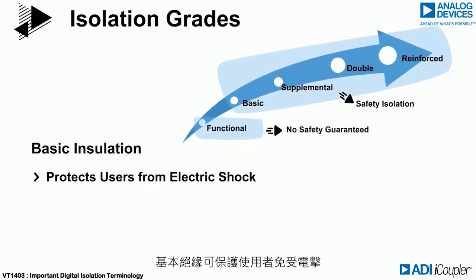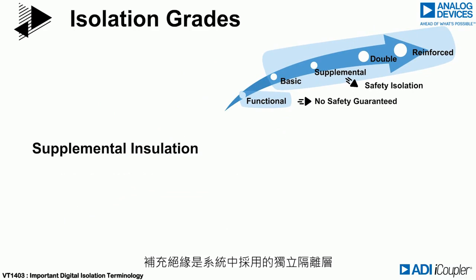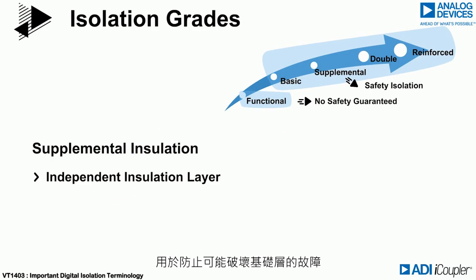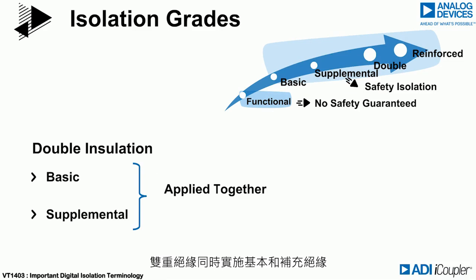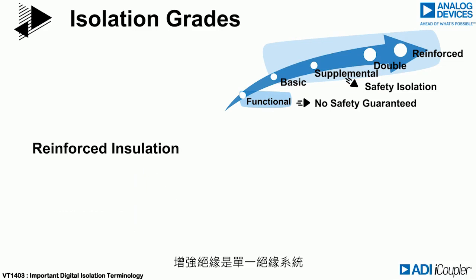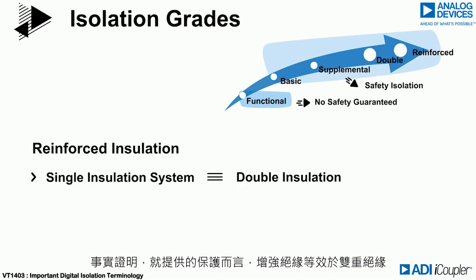Basic insulation protects users from electrical shock. Supplemental insulation is an independent insulation layer applied in a system to protect from faults that might breach a basic layer. Double insulation is both basic and supplemental insulation applied together. Reinforced insulation is a single insulation system that's demonstrated to be the equivalent to double insulation in terms of the protection provided.